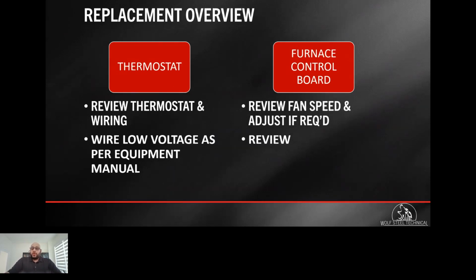You're going to want to run your thermostat wiring, install and program your thermostat. Read the manufacturer's directions, as on some equipment you will need to run the reversing valve on cooling or the reversing valve on heating based on the specification. And then based on the size of the heat pump, you're going to want to adjust any dip switches to set up the proper CFM for the equipment that is installed.